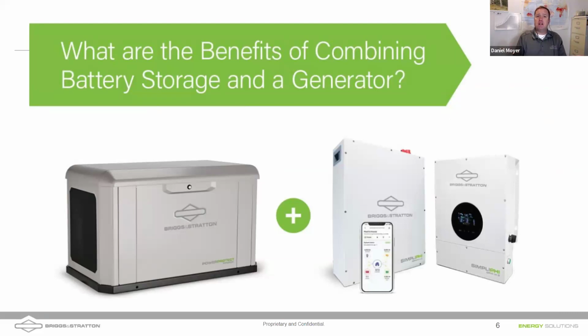So what are the benefits of combining battery storage and a generator together? As I kind of hinted at a minute ago, in a lot of ways the photovoltaic industry and battery industry got its start in the off-grid market. And in off-grid installs, we would always combine a generator. Why? Because if I have to size a photovoltaic system to get you through the dead of winter, it's going to be way oversized in summer. And you're probably going to spend more money on that solar array, especially back in off-grid days when solar was really expensive, than you might otherwise need. We would combine a generator in off-grid systems and allow you to charge up those batteries when it was cloudy out, when it was dark out.